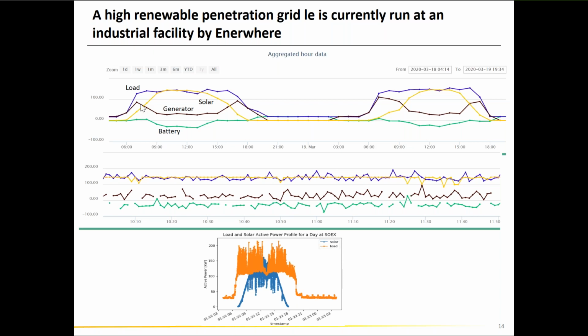Now we're using the batteries here for mainly two or three things. One is, of course, frequency stabilization. Before we got onto this site, the frequency this client was operating at was varying between 49 and 51, because of those crazy peaks and the generators not being able to hold that frequency. The batteries have improved that dramatically, and we've been able to move from that range to maybe 49.8 to 50.1. We've brought that in closely.